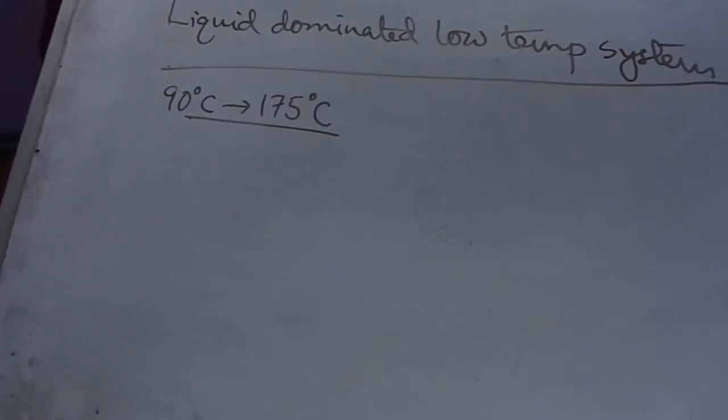The geothermal fluid is re-injected after extraction of heat. This vaporized fluid serves as a working fluid for the turbine. The exhaust vapor from the turbine is cooled in the regenerative heat exchanger and then condensed in the condenser.